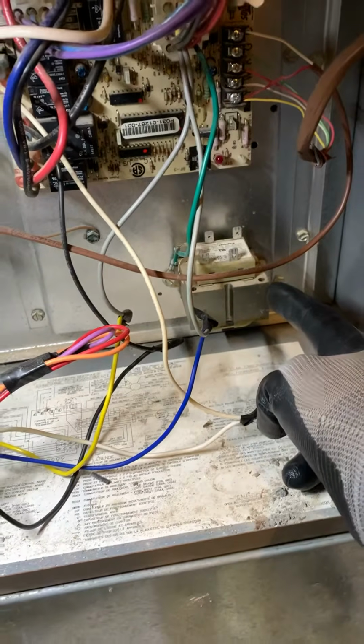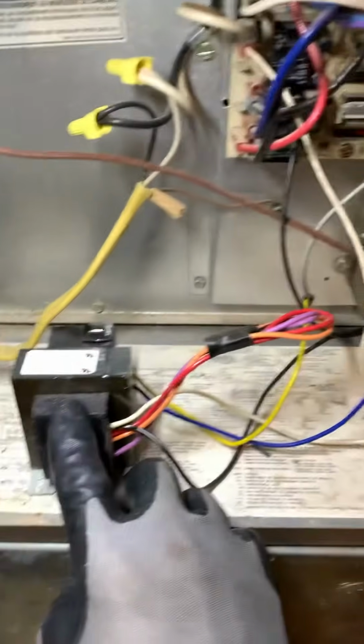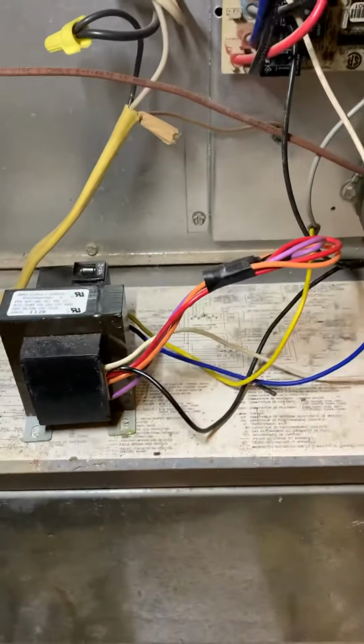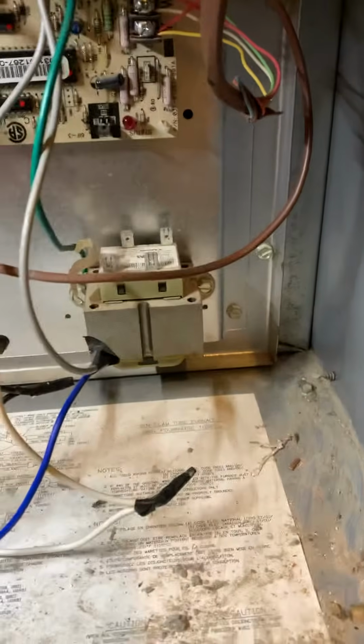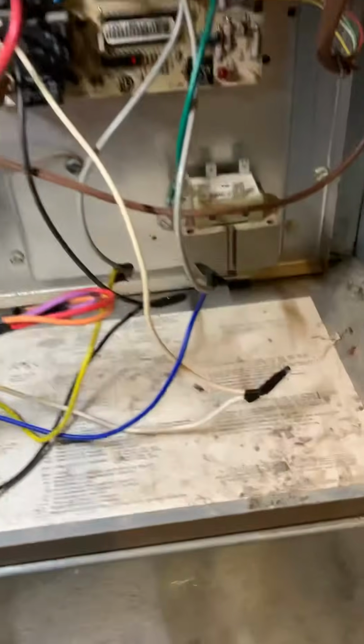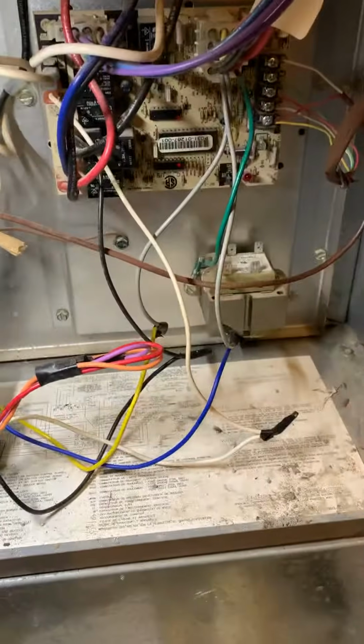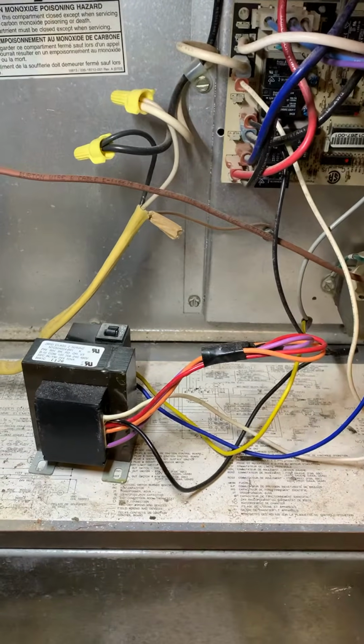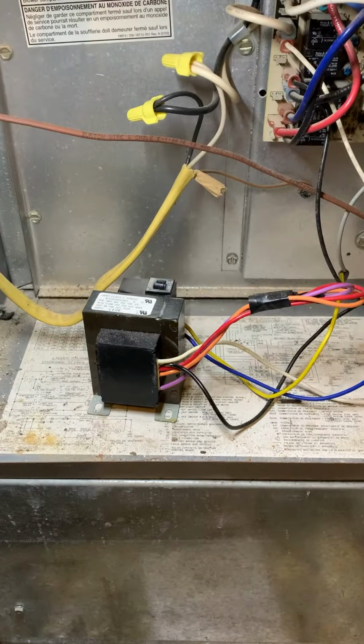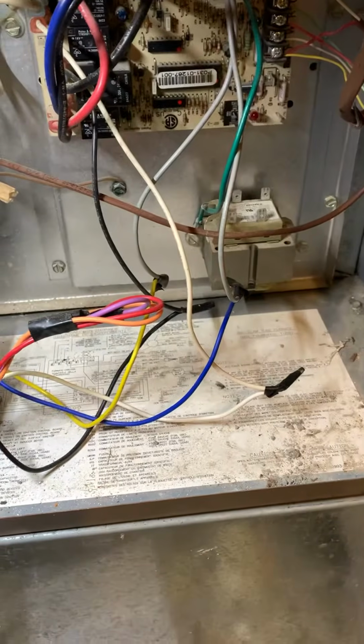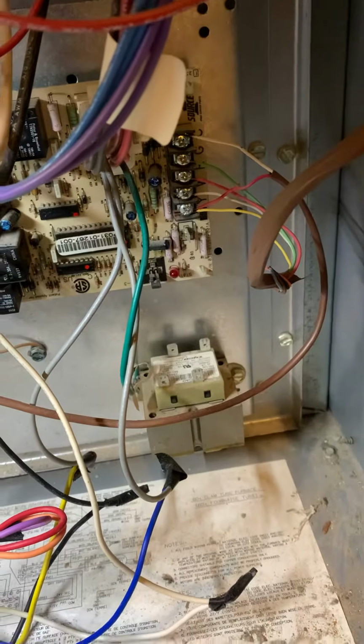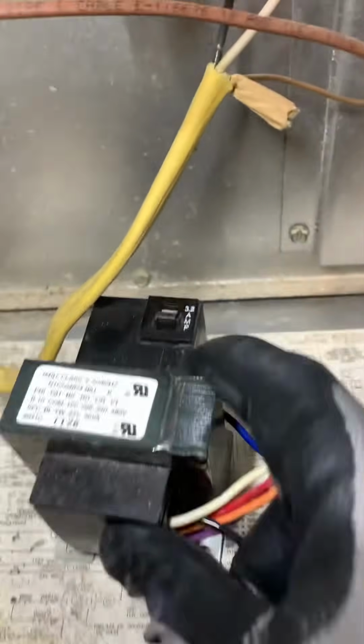So they had an issue with the old transformer. Okay, so instead of taking that out and replacing it with this one here, swapping them, taking it out and putting that there, I understand it's bigger, but I'm sure we can get a screw in there, somewhere to lock it in. If we can't, I could put it to the side here or to the side there, not so that it's just hanging out over here like this. At the same time, no wire nuts. So I'm going to have to wire nut these up, mount that safely, okay? And it was the contactor. So the coil on either side was giving an issue, because it had way too much amperage coming through. That light was going crazy, and then it would pop this little 3.2 amps, okay?